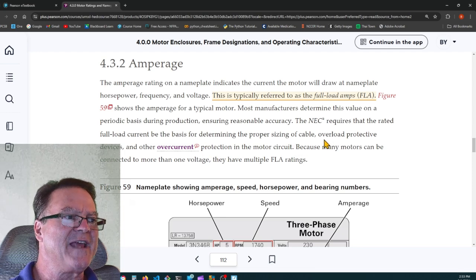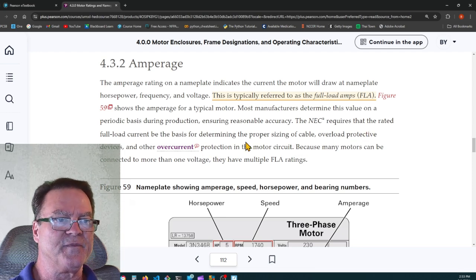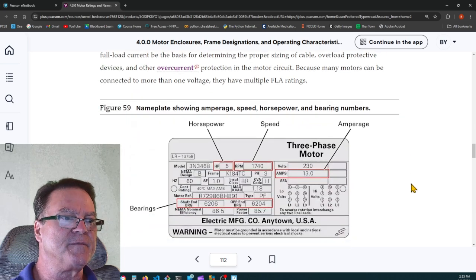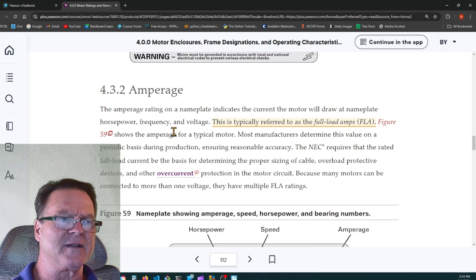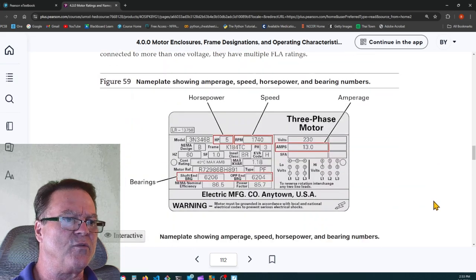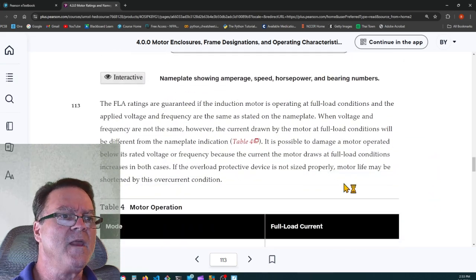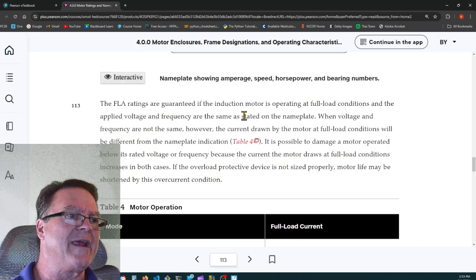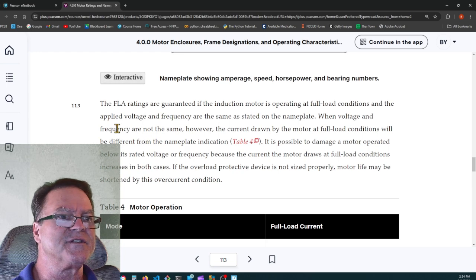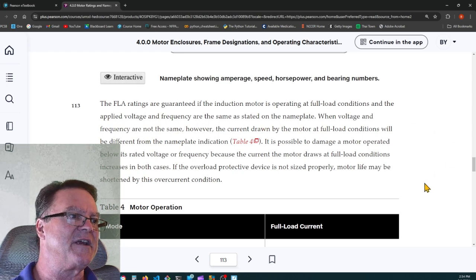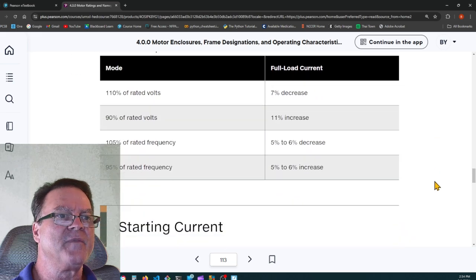The only thing we'll use the nameplate for is the overloads. We will go by the nameplate rating amperage for the overloads. That's in 430.6. You can see that in the code book. Full load amp ratings are guaranteed if the induction motor is operating at full load conditions and the applied voltage and frequency are the same as stated on the nameplate.